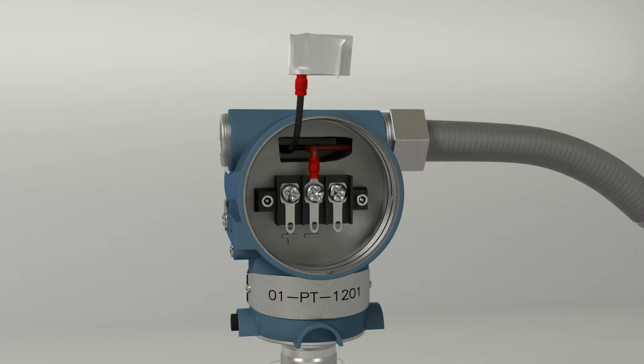Next, remove the negative wire from the terminal in the transmitter. This wire can touch the casing. It will not short on anything except for the positive wire that is wrapped in tape, so we are safe. Now we want to tighten the screw terminals again, so that there is no error in our 4 to 20 milliamp signal during the calibration.